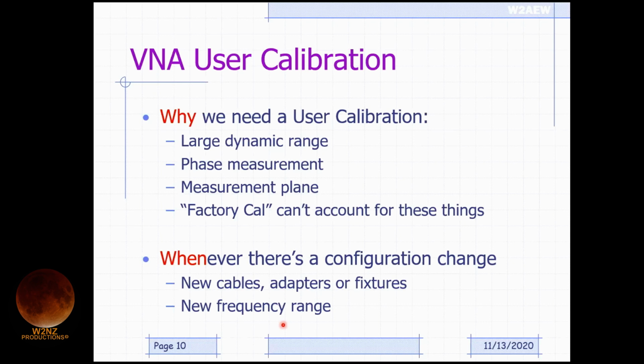That's a good question. It depends. Let's say I calibrated my unit from, say, 14 megahertz to 14.3, and I maybe shifted my measurement range to be 14.05 to 14.2 or something like that. That's probably close enough that as long as your VNA interpolates between calibration points, you're probably okay. But if I set up a measurement range over, say, the 40 meter band, and then I changed to, say, the 15 meter band, I'd probably want to recalibrate.